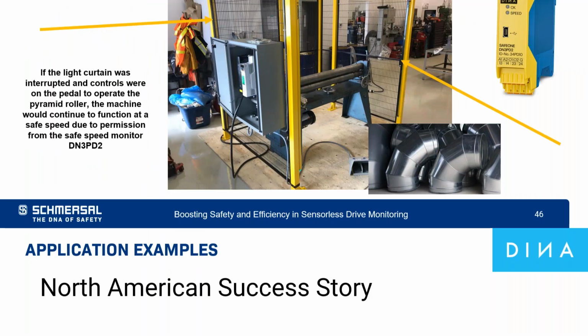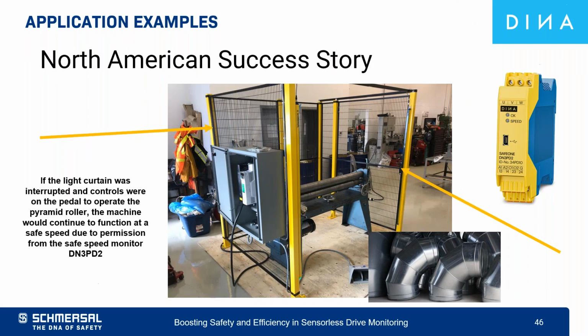If you broke the light curtain beam while it was in operation with more than just the sheet metal, like your hand or your leg, the pyramid roller would reduce to a safe speed of less than 250 millimeters per second. The DINA DN3PD2 took care of this function by not putting the machine into an e-stop if the pyramid roller was running at the correct speed. If the curtain was unobstructed, the machine would run at a normal speed of 430 millimeters per second. The slowdown time between the 2 speeds was less than 1/10 of a second, which met the requirements of getting access to the hazard at a safe speed.